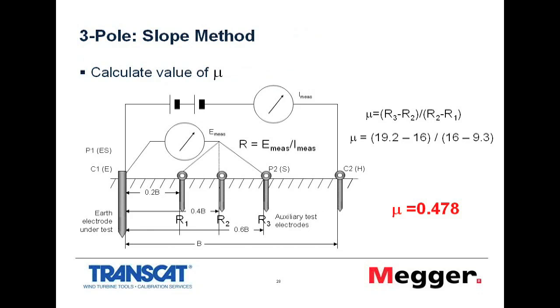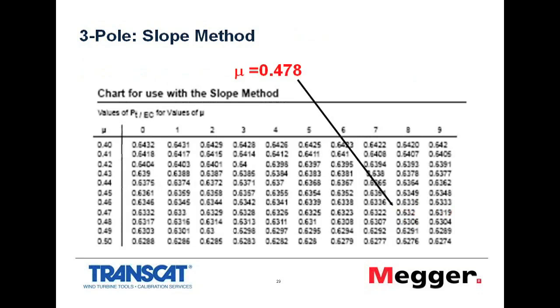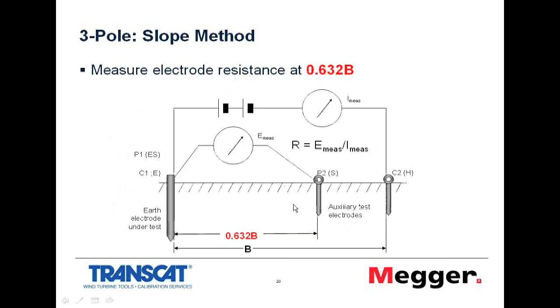That value then I will look up in a chart. I apologise for the slight fuzziness of this chart, but I would take that value, which is 0.478, and where that crosses here, I now have a value of 0.632. Now what that is telling me is that if I place my voltage probe at 63.2% of the distance between the system earth I'm measuring and the current probe, at that position I will measure the actual resistance of the earth system.